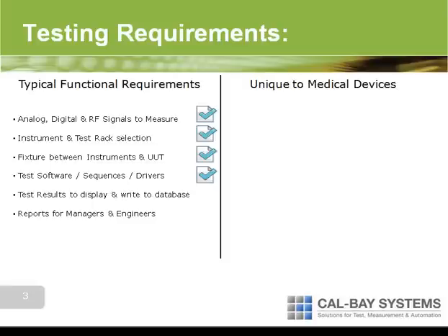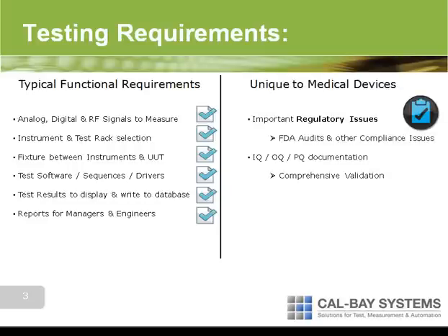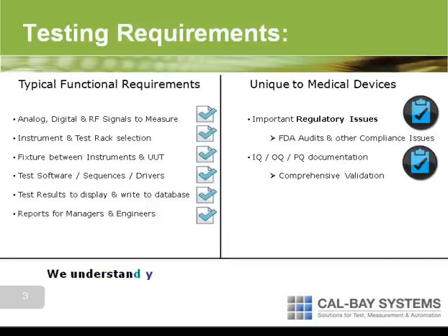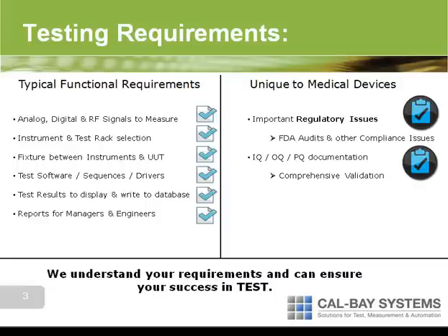Operators need to see whether the UUT passed or failed, and the test results need to be written to databases and shared with your MES or ERP. Finally, managers and engineers need high-level reports of the data. In the regulated world of medical devices, compliance is key. Documents like IQs, OQs, and PQs must be written for each ATE, and all components must be documented and qualified thoroughly. Having a scalable hardware and software platform is critical since it minimizes the time that must be spent on validation. Luckily, CalBay builds ATE systems every day with tremendous experience of the medical device ATE process. The bottom line, we understand your requirements and can ensure your success in test.